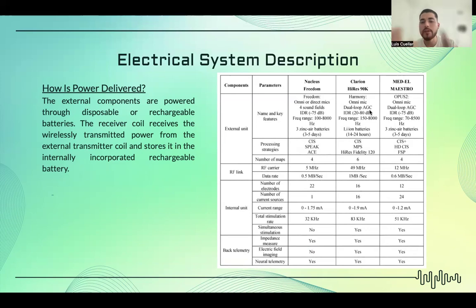The input dynamic range is what helps determine how cleanly different sounds are picked up, right? Sometimes if you have a low input dynamic range, some cochlear implants make really loud noises muddy, and really soft noises are not picked up at all. So increasing the input dynamic range allows it to pick up those sounds more clearly. This is, in a way, part of the innovations of the cochlear implant that we're seeing nowadays. I don't really talk much about it in my key innovation section, but I think it's worth mentioning that companies nowadays are striving to improve the input dynamic range so that there is a better way for sound to be picked up by the cochlear implant.